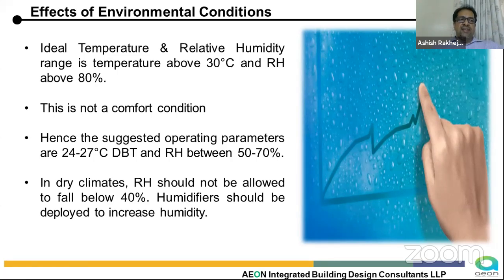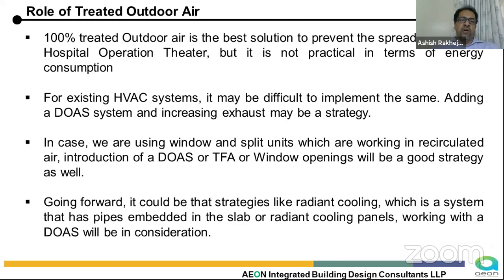What's important is the ventilation rate also plays an important role. Ideally, as Dr. Chandrasekhar was saying, we'd like to have an open system with 100% ventilation - that would be the best thing to go for. But that's not what is possible in current healthcare facilities when we are looking at minimizing dust particles, because our outdoor air quality is not exactly very clean. So elevated outdoor air additions are important. The guidelines are available in the systems.